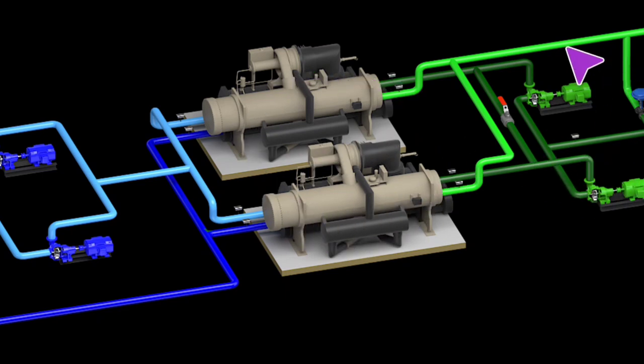By running 85 degree water on the cooling tower, sure you might be able to reduce those fan speeds from say 100% down to maybe 80%, so you reduce your amp load by 15-20 amps total. You end up increasing your chiller load by a solid 50-60 amps in many cases. The net value just doesn't work out that way.